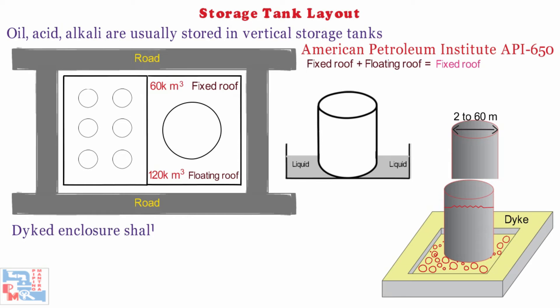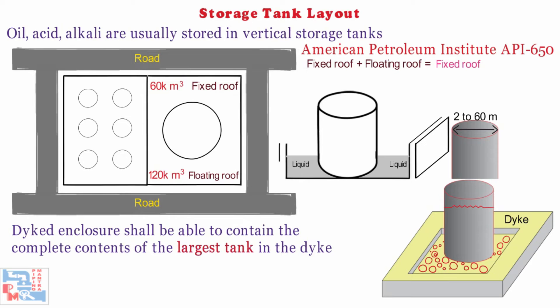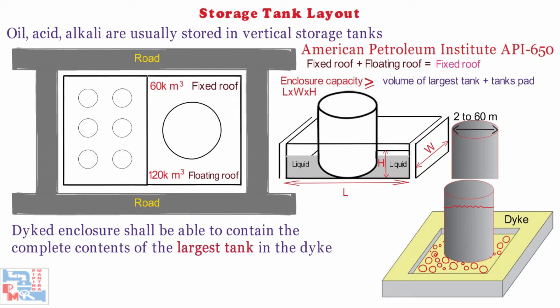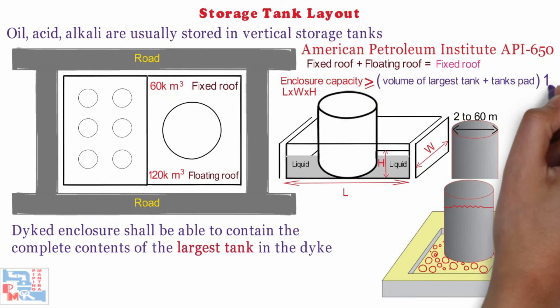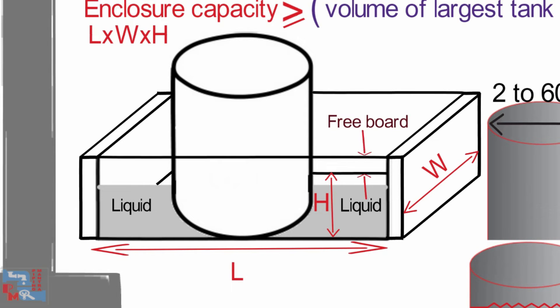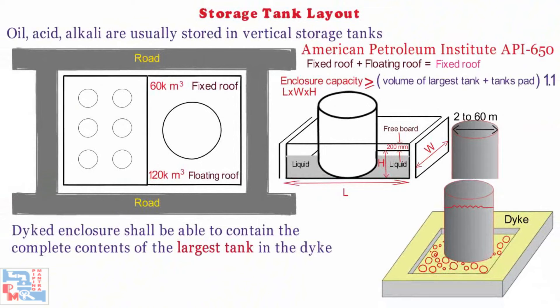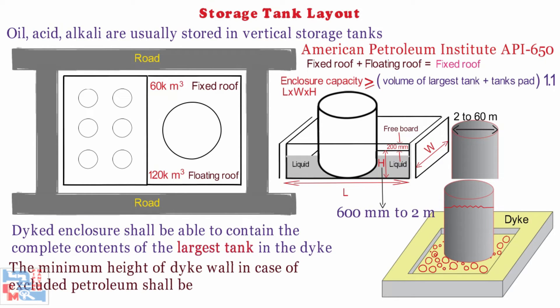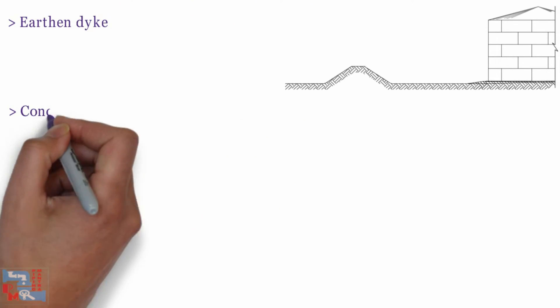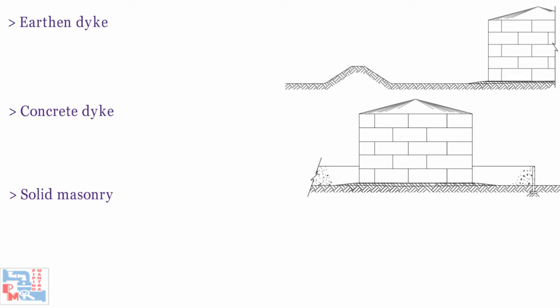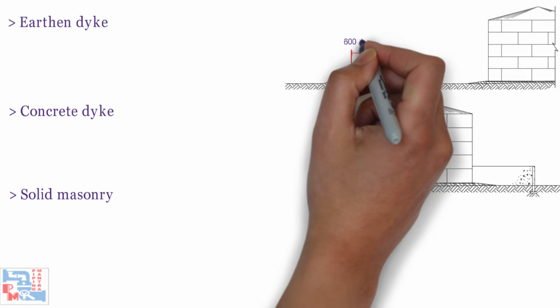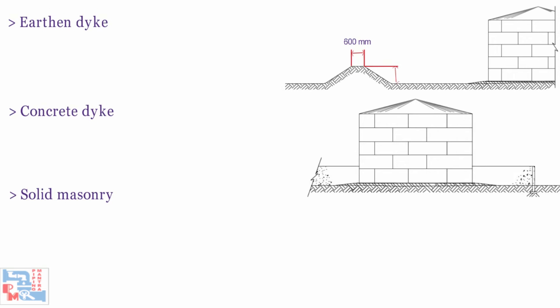The dike enclosure shall be able to contain the complete contents of the largest tank in the dike in any emergency. The enclosure's capacity — volume L × W × H — shall be equal to or greater than the volume of the largest tank and tank-pad volumes within the dike, with at least 10% added for safety. A freeboard of 200 mm above the calculated liquid level shall be considered for fixing the dike height. The dike height including freeboard shall be at least 600 mm and shall not exceed 2 meters above average inside grade level. The dike wall — made of earth, concrete, or solid masonry — shall withstand hydrostatic load. Earthen dike walls shall have no less than 0.6 meters wide flat section on top, a minimum height of 900 mm, and a width-to-height ratio of 1.5 to 1.